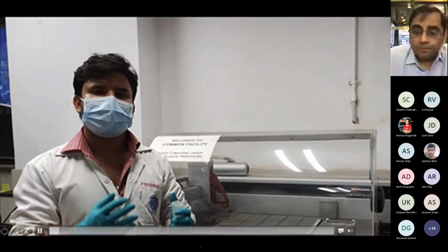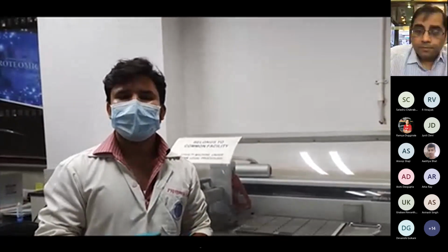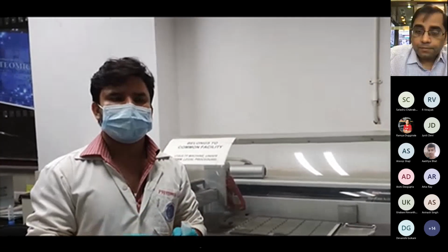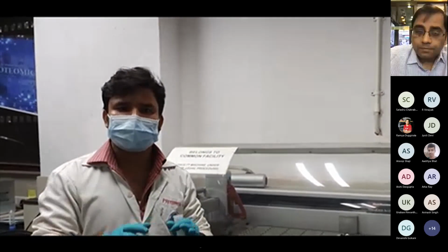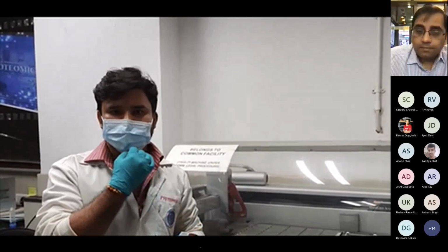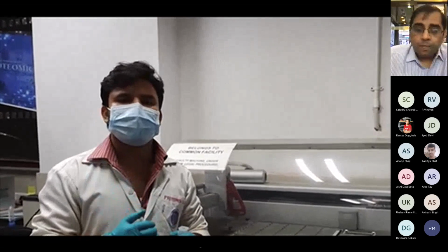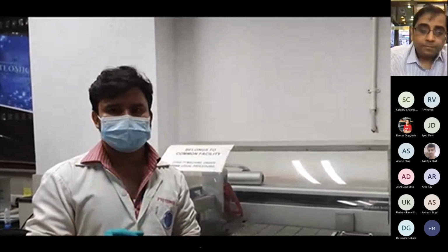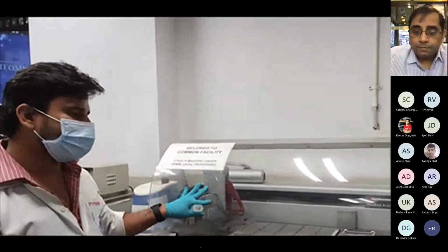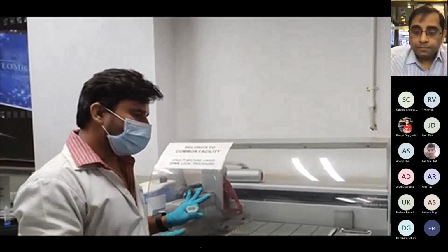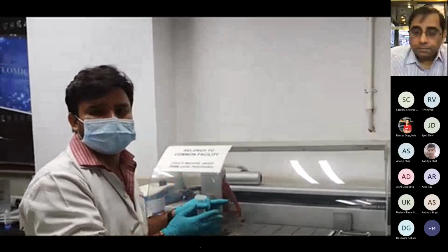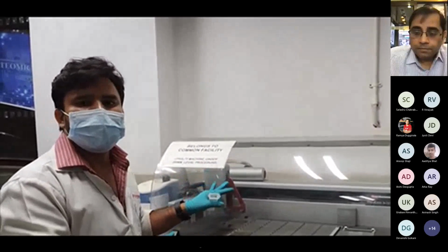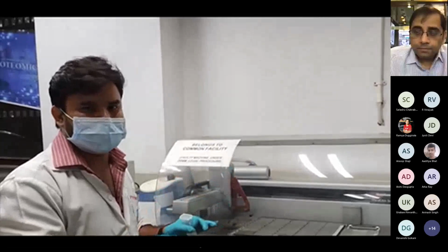Okay, so the slide we showed was a eukaryote array, right? And in the eukaryote array, we mentioned that it has 19,000 proteins in duplicates. So overall, the spots are around 45,000. So it covers the whole human proteome in a single slide. But how to make those slides? It is not very easy to put 45,000 proteins in a single small slide. So for that we have the microarray printer, where we can give commands for different proteins, and if we give the dimension or location, it will print those proteins automatically in a very precise way.